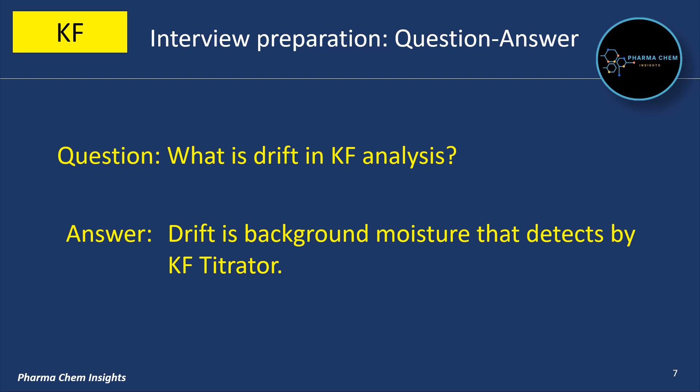What is drift in KF analysis? Drift is the background moisture detected by the KF titrator. The moisture present in the titration vessel is called background moisture.